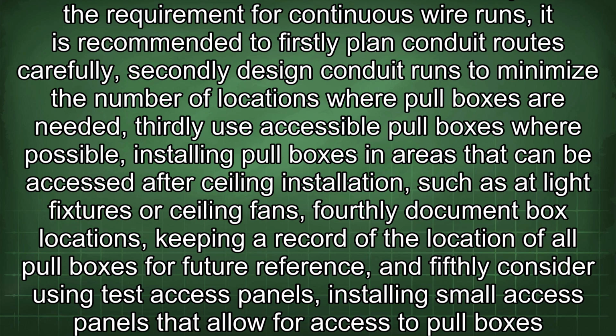To address both the need for accessibility and the requirement for continuous wire runs, it is recommended to firstly plan conduit routes carefully, secondly design conduit runs to minimize the number of locations where pull boxes are needed, thirdly use accessible pull boxes where possible, installing pull boxes in areas that can be accessed after a ceiling installation such as at light fixtures or ceiling fans, fourthly document box locations, keeping a record of the location of all pull boxes for future reference, and fifthly consider using test access panels, installing small access panels that allow for access to pull boxes above the ceiling if deemed necessary.